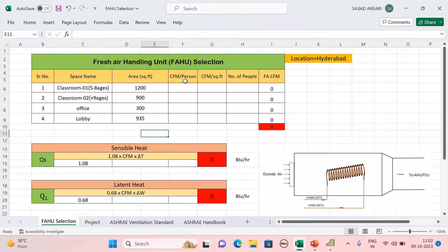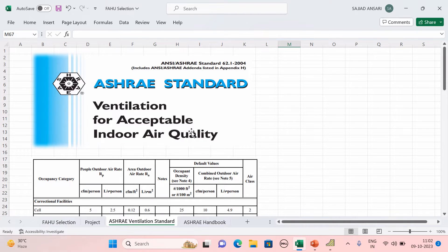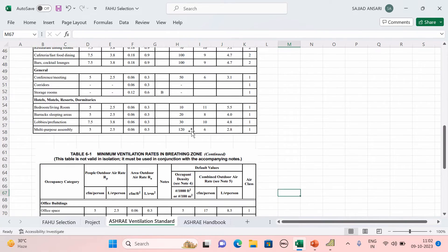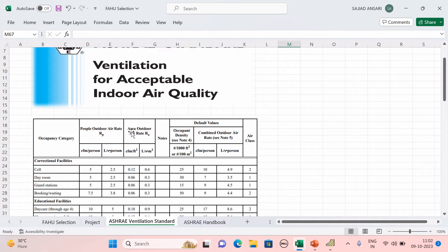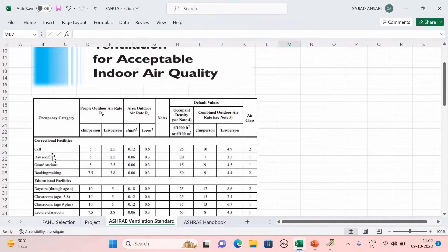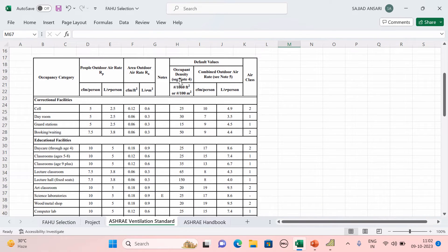Next we need to find out the CFM per person value. This value — CFM per person and CFM per square feet — you get from the ASHRAE ventilation standards. Opening that now: when you open Table 6.1, Minimum Ventilation Rate in Breathing Zone, based on occupancy category they give you CFM per person and CFM per square feet values.